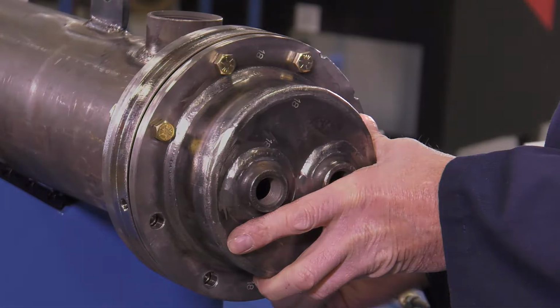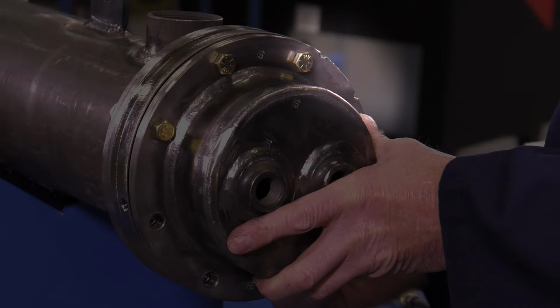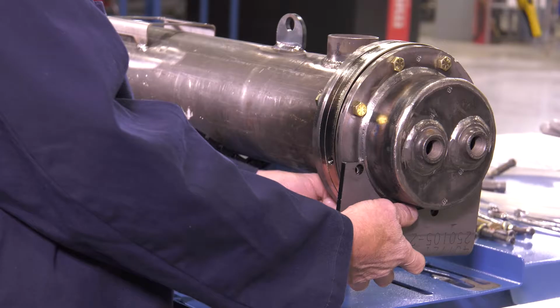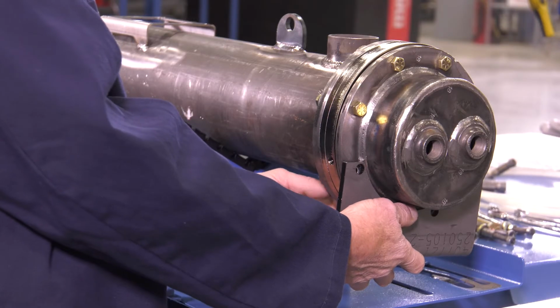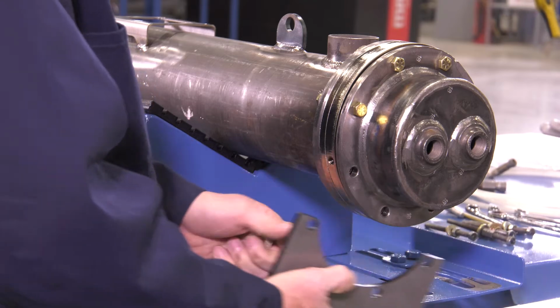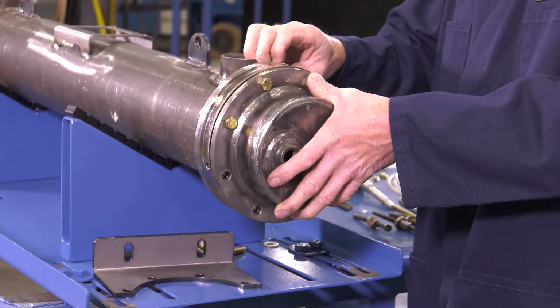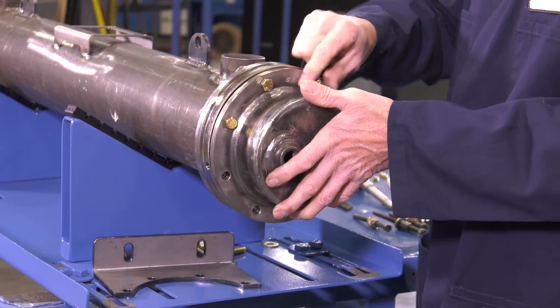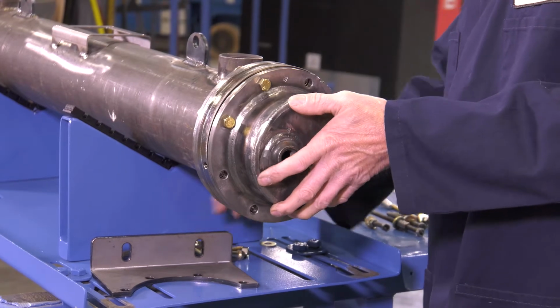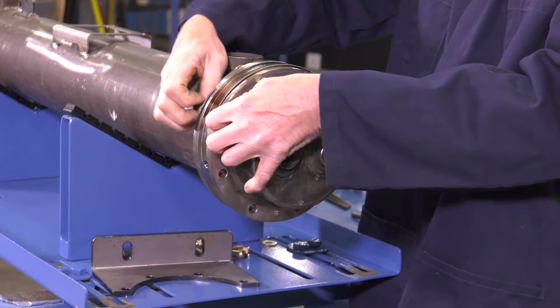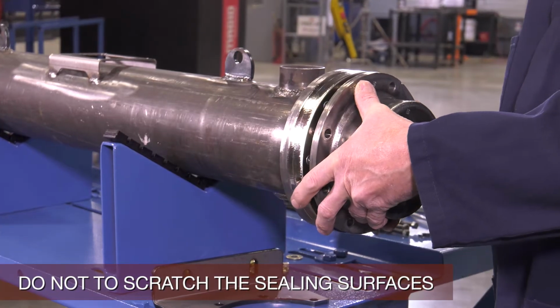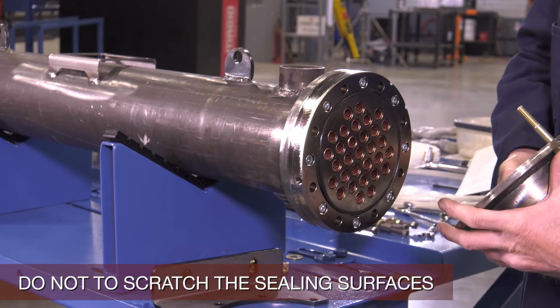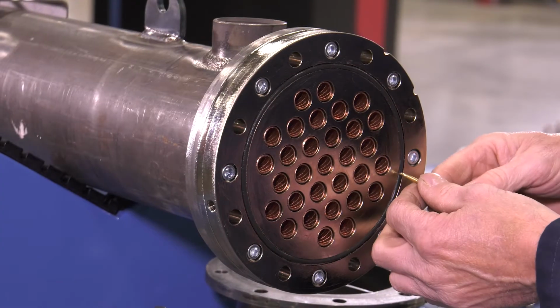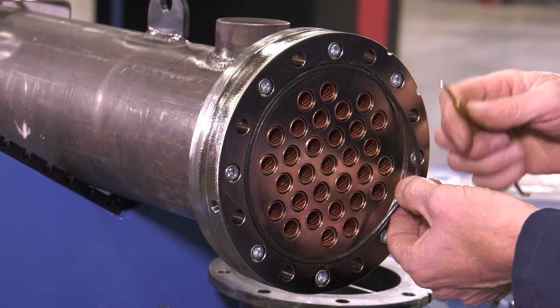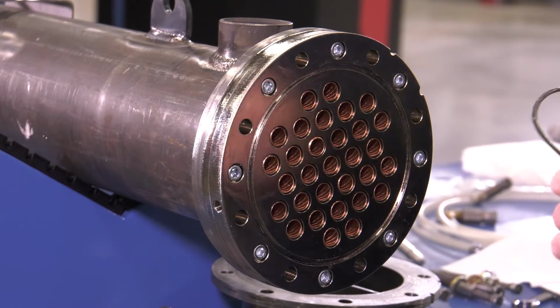Note the orientation notches on the end tanks, header plates, and the shell flanges for reinstallation. Note the orientation of the mounting feet so they can be reinstalled in the same orientation. Remove tank end retainer bolts, nuts, washers, feet, and both end tanks. Mark which side the tank ends are removed from, as they may be different. Carefully remove and clean the O-ring seal off the header to tank end.